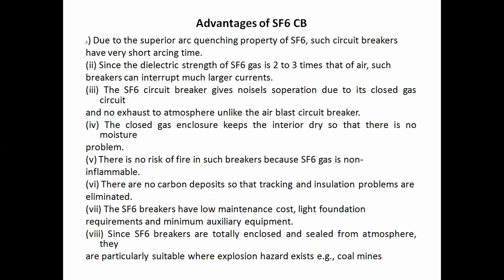So again, these are certain advantages of the SF6 circuit breaker overall. Due to the superior arc quenching property, SF6 circuit breakers have a very short arcing time. Since the dielectric strength of SF6 is 2 to 3 times that of air, this type of circuit breaker can be used over a large current value. So there are certain advantages of this type of circuit breaker.